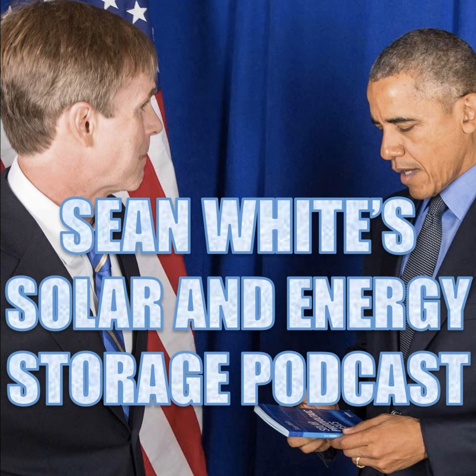However, when you charge a lithium battery, there's no danger of making hydrogen gas, so there's no reason to have ventilation. Just think of your cell phone in your pocket or your computer. We're not gassing off hydrogen from these lithium batteries. So in a way, they're safer. You can't build up some explosive gas from a lithium battery. So just make sure that it is appropriate for your energy storage technology, which means with lithium, skip it. And most people are doing lithium these days, so you can skip it.